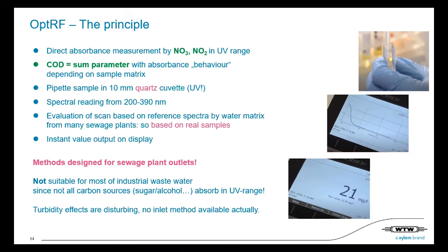And we are measuring in the outlet here. We pipette the sample into a 10 millimeter quartz cuvette. The spectra is read from 200 to 390 nanometers.